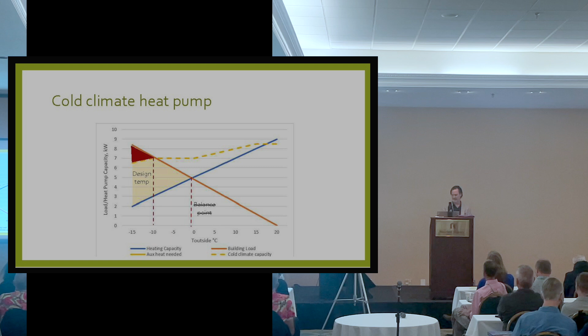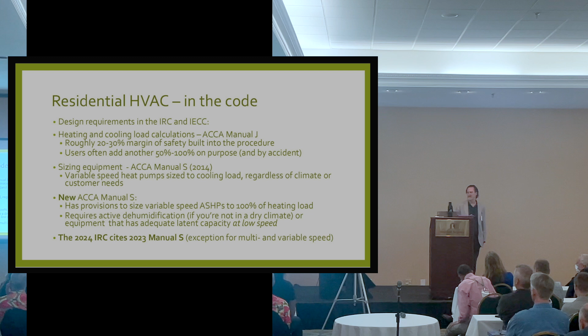So I'm going to talk a little bit about code because later on I'm talking a little more about regulations. The International Residential Code and the IECC have references to ACCA Manual J for load calculations and Manual S for sizing and selecting equipment. And Manual S, forever, when you look up heat pumps in that section, says you need to size them for the cooling load. No more than, it gives you a little bigger margin for variable speed systems, 120% maximum of the design cooling load, and you're on your own. You've got to provide some sort of electric or other auxiliary heat for the heating design condition.